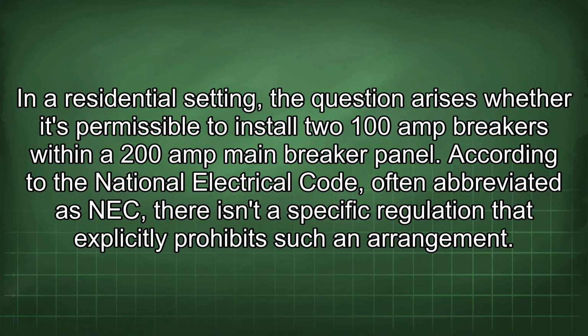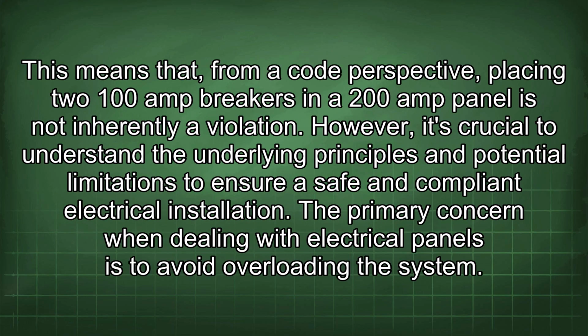In a residential setting, the question arises whether it's permissible to install two 100-amp breakers within a 200-amp main breaker panel. According to the National Electrical Code, often abbreviated as NEC, there isn't a specific regulation that explicitly prohibits such an arrangement. This means that, from a code perspective, placing two 100-amp breakers in a 200-amp panel is not inherently a violation. However, it's crucial to understand the underlying principles and potential limitations to ensure a safe and compliant electrical installation.